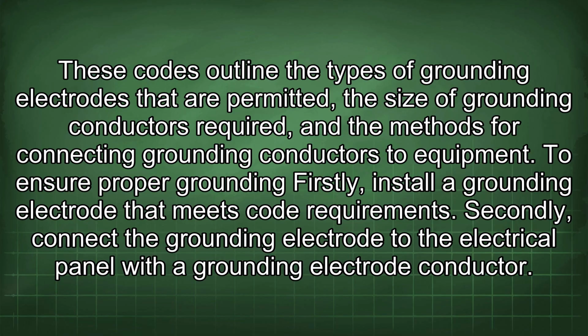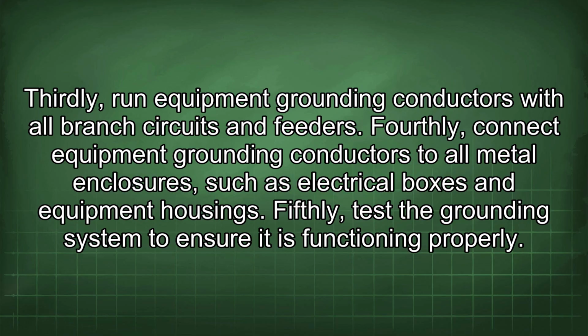To ensure proper grounding, firstly, install a grounding electrode that meets code requirements. Secondly, connect the grounding electrode to the electrical panel with a grounding electrode conductor. Thirdly, run equipment grounding conductors with all branch circuits and feeders. Fourthly, connect equipment grounding conductors to all metal enclosures, such as electrical boxes and equipment housings. Fifthly, test the grounding system to ensure it is functioning properly.